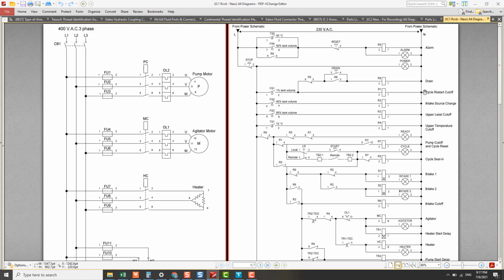If there is any slightly loose connection or a load with slightly high resistance, which we can treat like a normal load inside the common neutral line, then when we measure the voltage here, the current will flow through this line to point 2 and divide into two paths. One path goes to the multimeter, the other to the load, or a point where there is a slightly loose connection. So the multimeter will register voltage, but lower than 230 volt AC because there is a load at the common neutral line. So the voltage is divided into two different voltage readings.